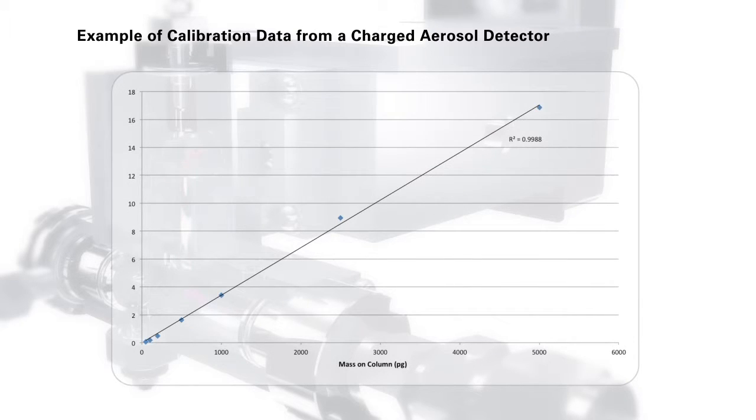For quantifying substances within a sample, calibration curves can be generated for up to four orders of magnitude in mass. Furthermore, the charged aerosol detector provides uniform relative responses; therefore, calibration with a single standard, even if not chemically identical, can be used to estimate the amounts of all sample components.